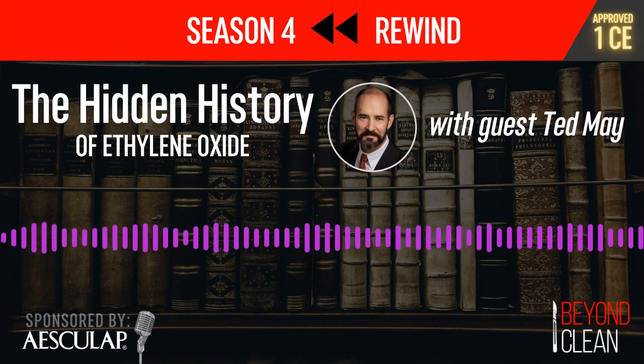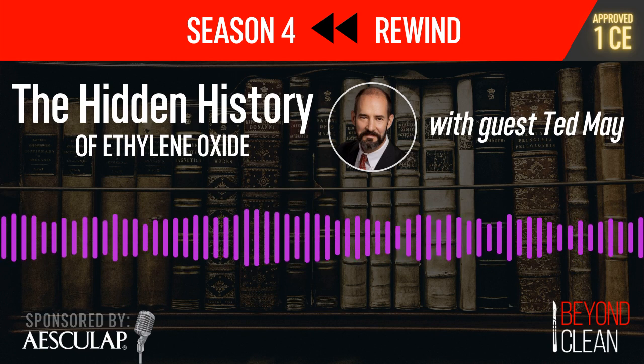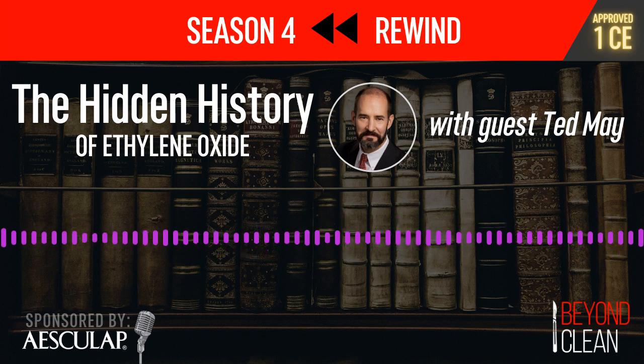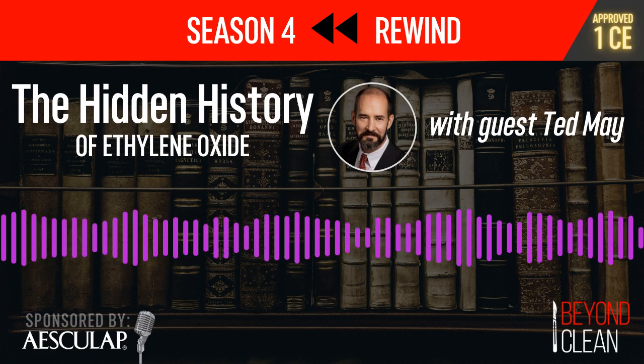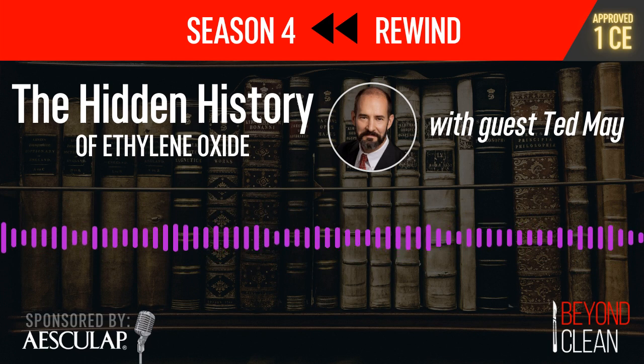This takes us into the 50s, and the first hospital-based systems were introduced really late 50s, and these were based on autoclaves. They were big metal chambers, run off of large 50-pound tanks. There weren't much in the way of controls, and there weren't much in the way of operator protections. And as many people know, ethylene oxide is not only flammable, it's highly explosive.